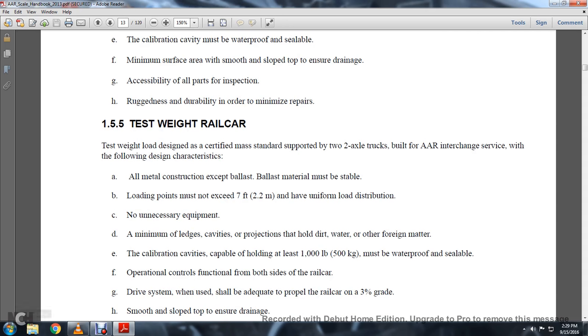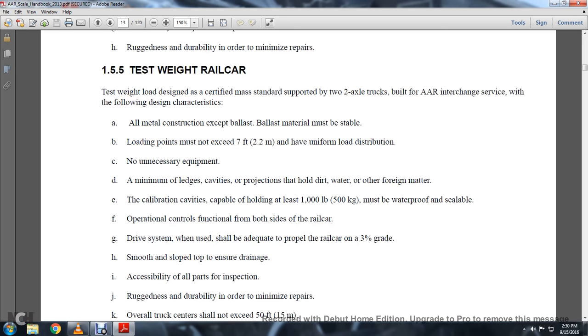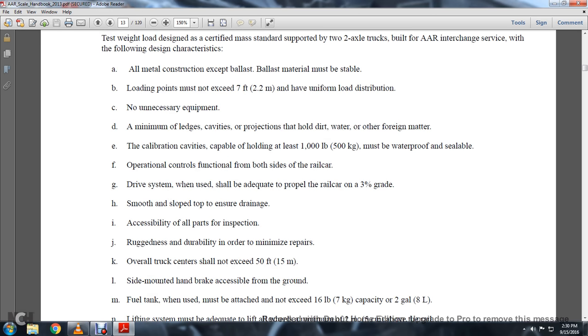All metal construction except for the ballast; ballast material must be stable. Loading points must not exceed 7 feet; uniform load distribution. No unnecessary equipment. Minimum ledges, cavities, projections holding dirt, water, and foreign material. Calibration cavities capable of holding at least 1,000 pounds must be waterproof and sealable. Operational control must be functional on both sides of the railway car drive system; when used, shall adequately propel the car on a 3% grade. Smooth and sloped top to ensure drainage; accessible parts for inspection; ruggedness and durability to minimize repairs.